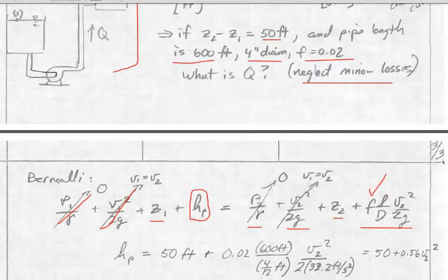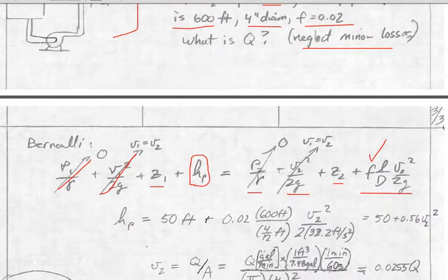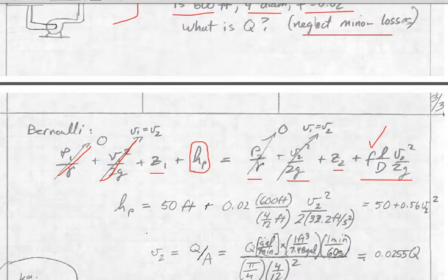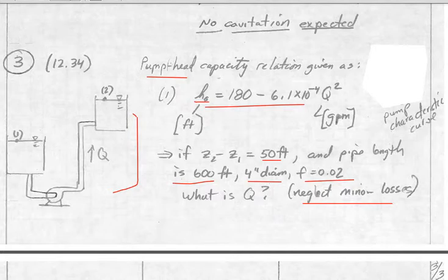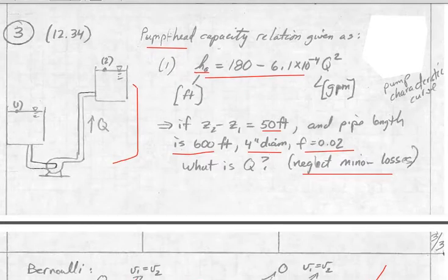So we're going to figure out a similar-looking curve called the system curve, where we solve for the head given by the pump by putting in all this other geometrical information. The only thing we don't really know is V squared, and so we end up with a curve that looks a little bit like this given curve. But remember, that's for head available, and that's coming out of the box with our pump.